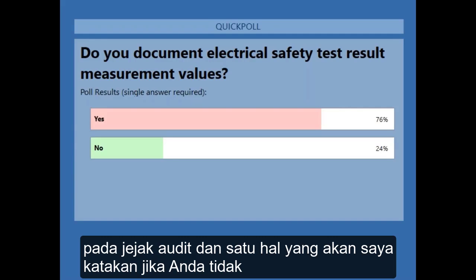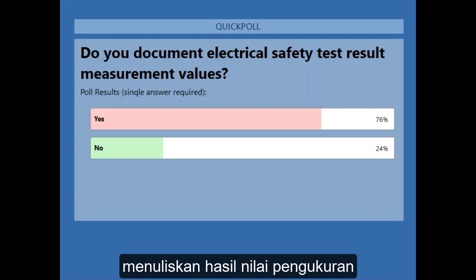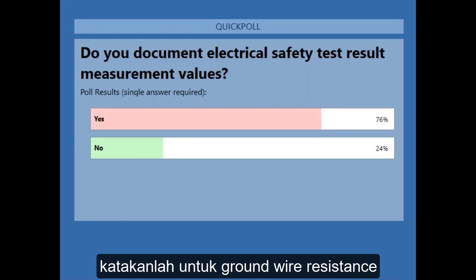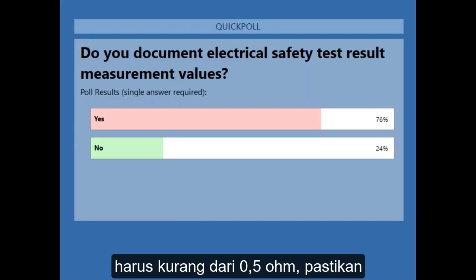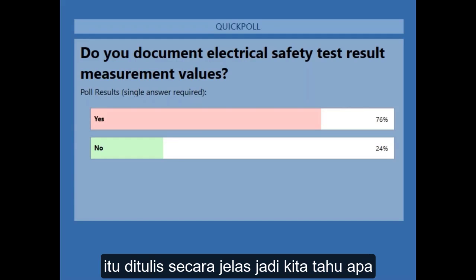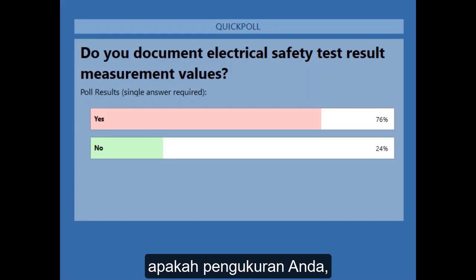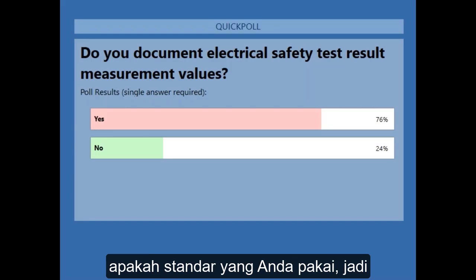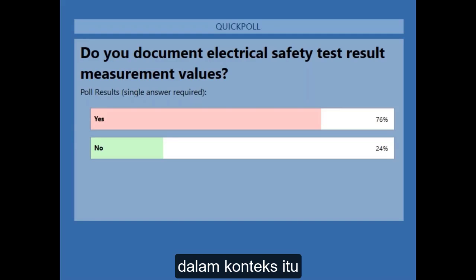And one thing I would say, if you are not putting down your electrical safety test measurement values, make sure that you have the standard, say for ground wire resistance, must be less than 0.5 ohms. Make sure that that's spelled out so they will know what is passing, what is your measurement, what is your standard that you're going against. That way you can look at it in that sense.